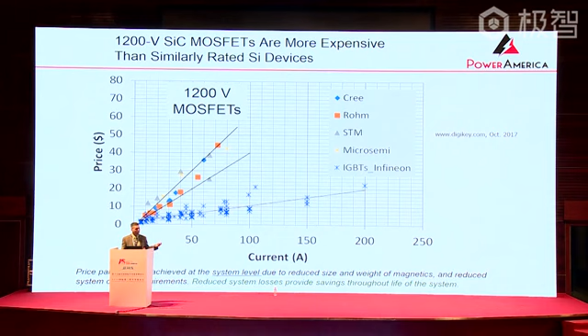But what happens if you go into a system? For this specific PV inverter, despite the fact that silicon is 3 times less in cost than the silicon carbide semiconductor, the overall system cost for silicon carbide is lower. Why is that? It's because when you use silicon carbide, you can operate at higher frequency, and as mentioned before, the cooling requirements are reduced because of the better thermal conductivity of this material.